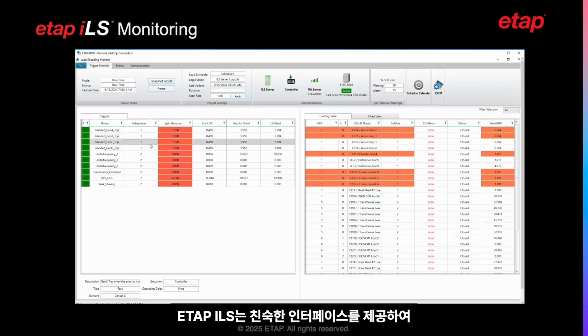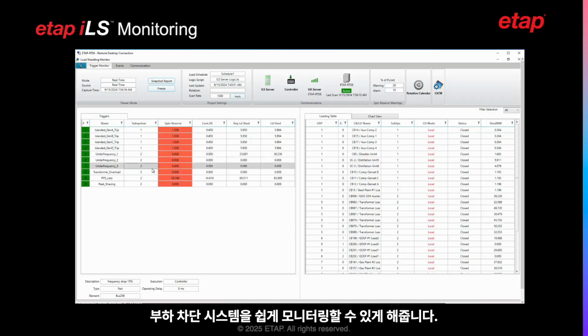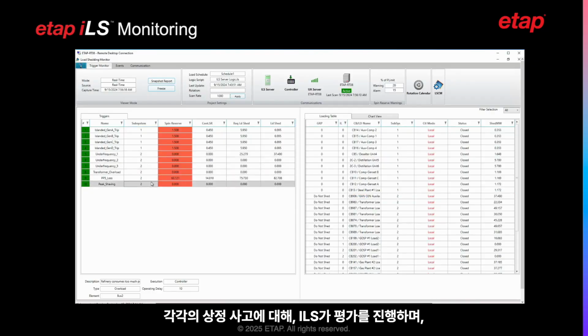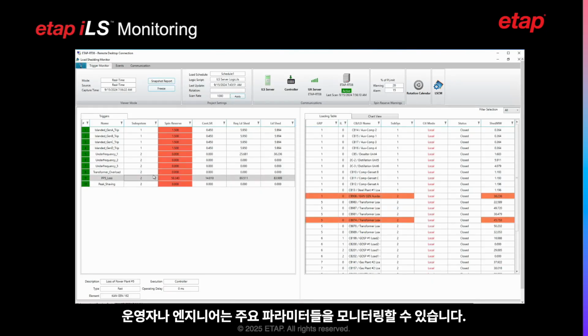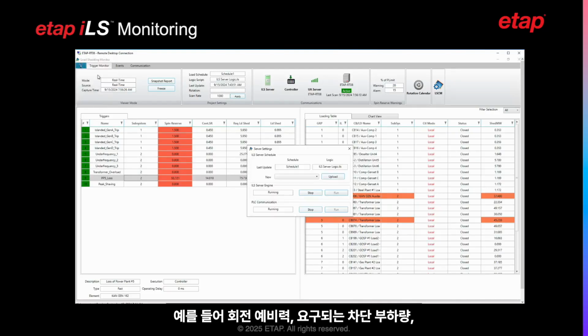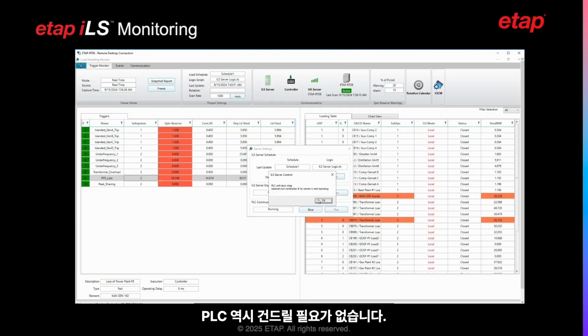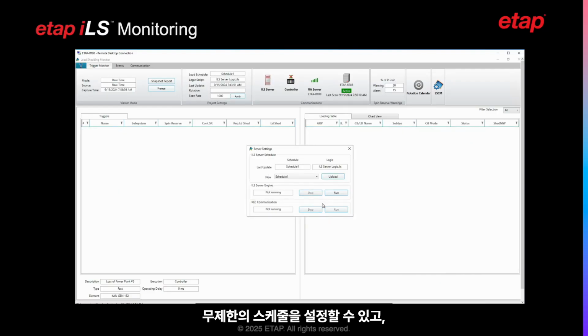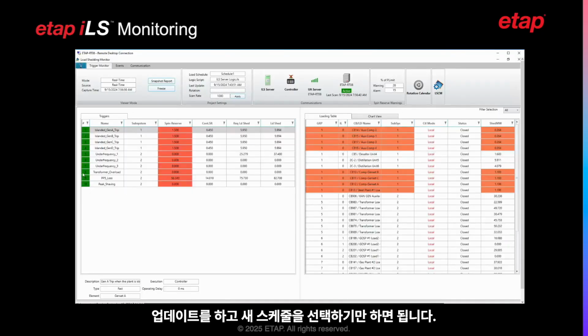ETAP ILS provides a friendly interface to monitor the load shedding system. For each contingency being evaluated by ILS, the operator or engineer can monitor critical parameters such as the spinning reserve, required load to shed, and actual load that will be shed if that contingency were to occur. ETAP ILS logic is available for engineers who've been granted the right permissions to perform modifications without going into the relays or PLCs to do so. An unlimited number of schedules can be set up and uploaded within the ILS system without the need to bring the system down. All we need to do is go to the server and update it and select the new schedule.